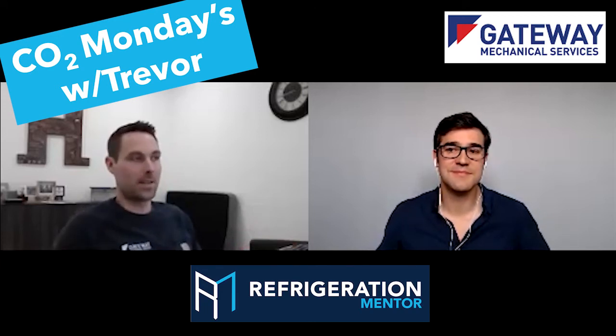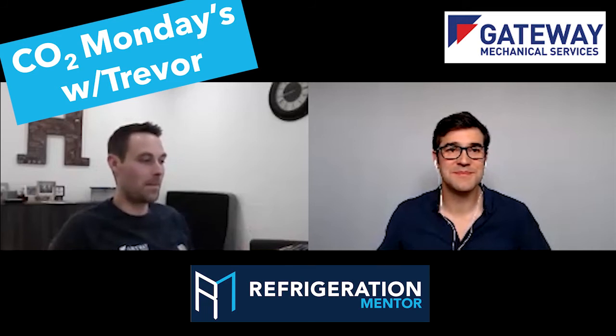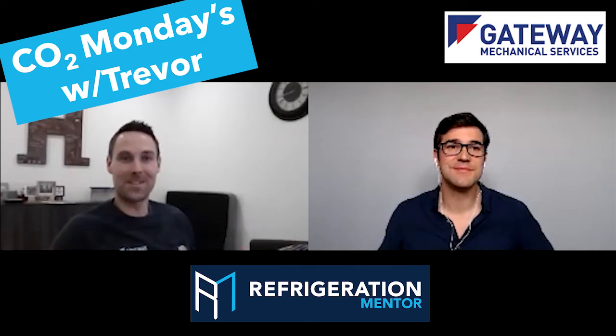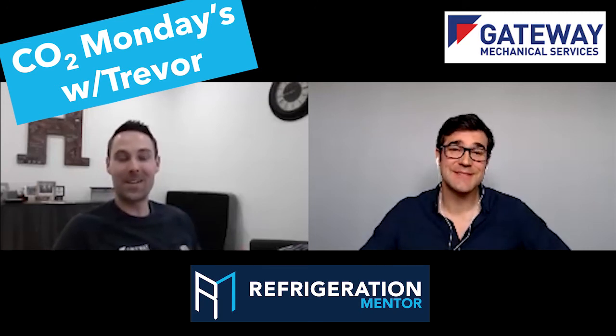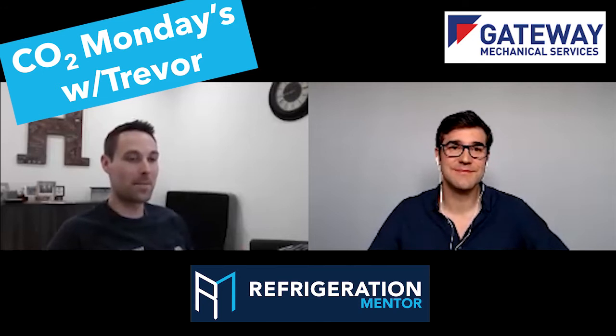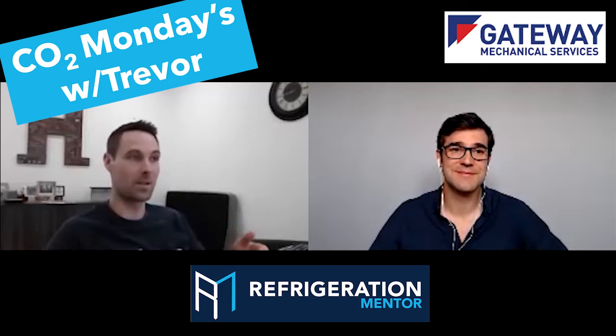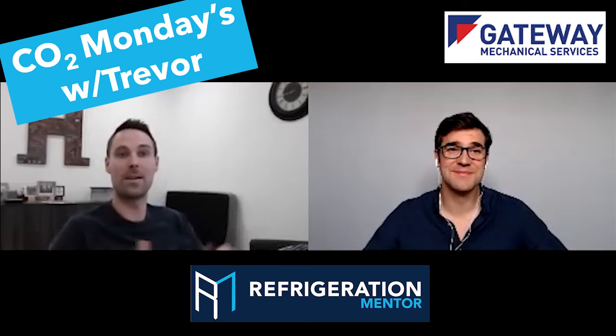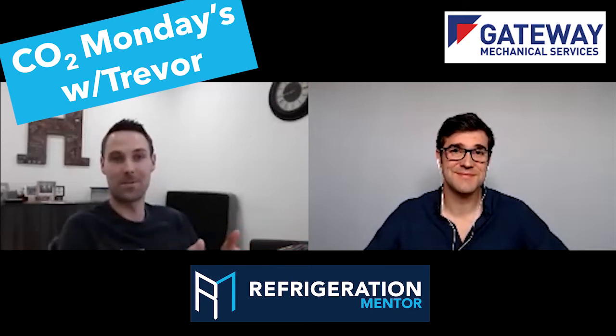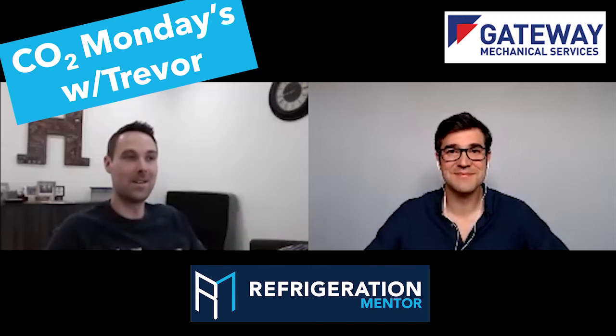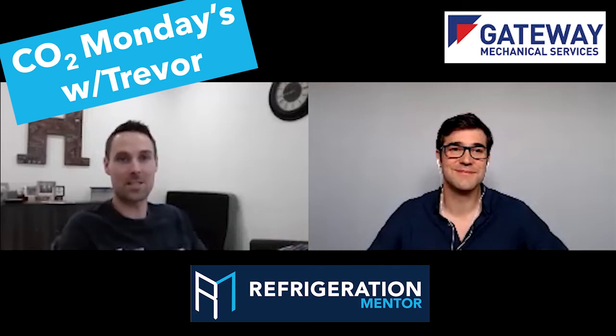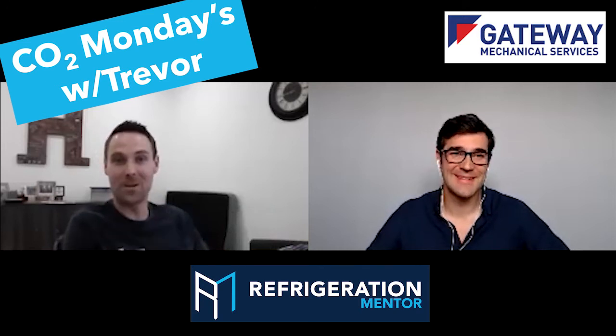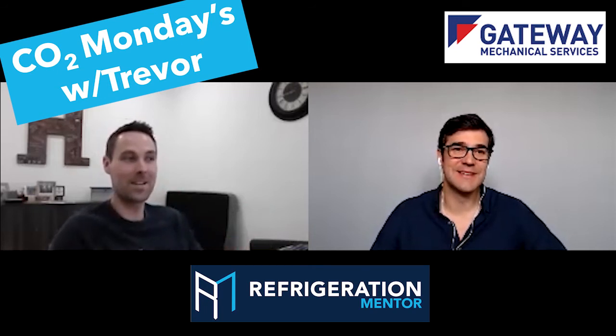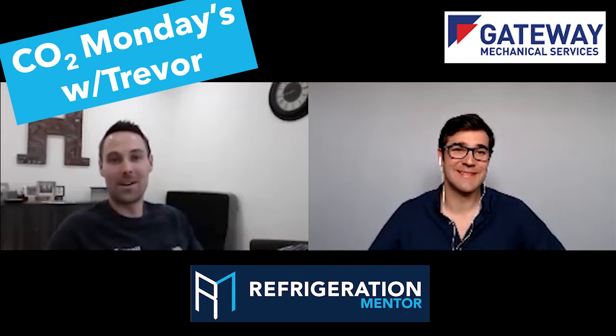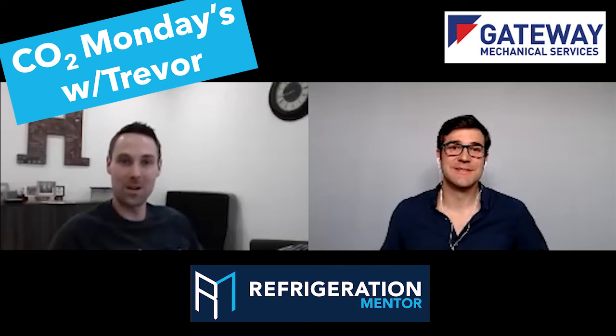And you know what? It's funny. A lot of people get really frazzled with VFDs, and I don't really understand why. When you really break it down, most of our HVAC applications, you have an enable for a VFD. It's like your start stop control. It's basically your controller saying, "Hey, this drive can start," and then a speed signal, and then you have all your related safeties. Once you break it down, it becomes less scary, and then people start to really like them, and they're like, "Oh man, this thing is awesome! It really keeps my pressure flatlined, and the system runs better." So I think it's getting over that hurdle of shock and awe, and then really getting into understanding, like, "Oh man, this is great." Yeah.